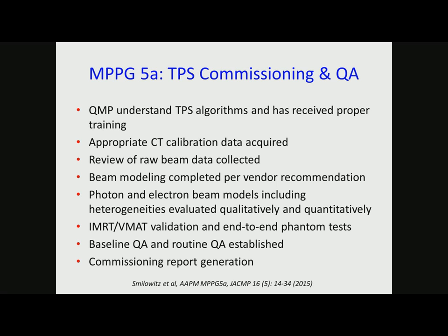Beam modeling is completed per vendor recommendation. Photon and electron beam models, including heterogeneity, are evaluated qualitatively and quantitatively. IMRT validation and the end-to-end test, like I suggested earlier. And then you set up the baseline QA. Once you're happy with all the commissioning work, you set up your baseline QA to do your TG-142 and to monitor your machine and your treatment planning system for the years to come.